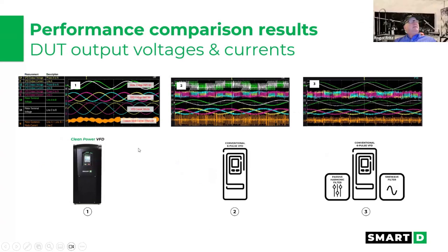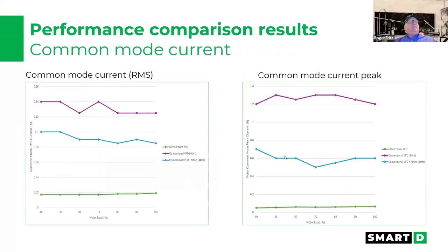So again, this is more of a detailed comparison of the output of the Smart D. Literally no common mode voltages. And we don't have all of these ripples, both in the input and output of the drive. And then this is a comparison to if you put a passive harmonic filter on and a sine wave filter output on a standard 6 pulse drive. And it is better, but we still have the same issue about this common mode voltage. So what ends up happening is you still have to put the grounding rings on, and you need to put long cable length filters on.